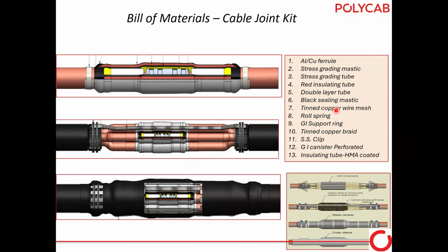Now copper screening is there. For the tin copper wire mesh, roll springs are there. GI support rings we use. Tin copper braid is there. SS clips are there. And GI canister over that. This is one canister. And over that the insulating tube is there. This is the insulation tube. Once we do all these, our joints are ready.